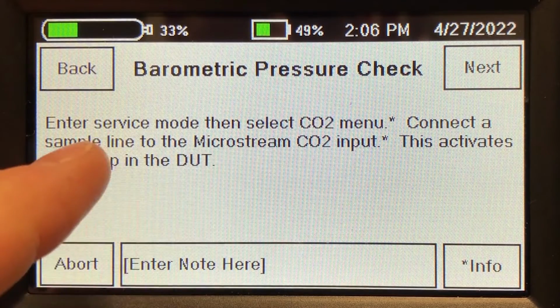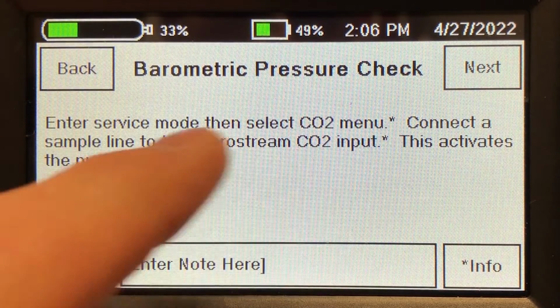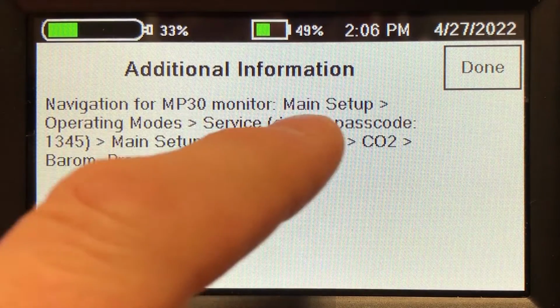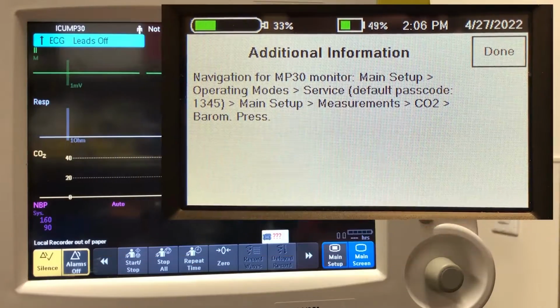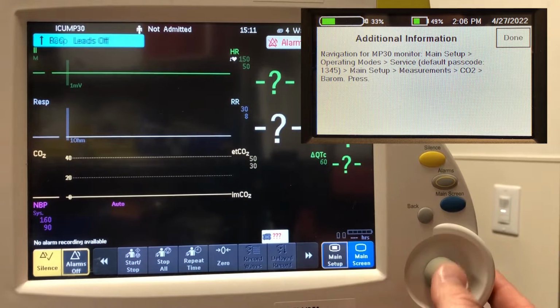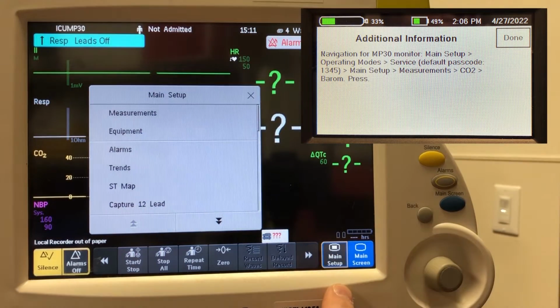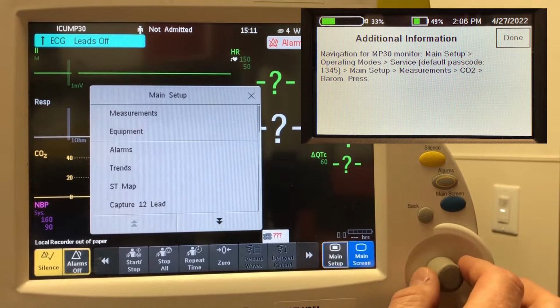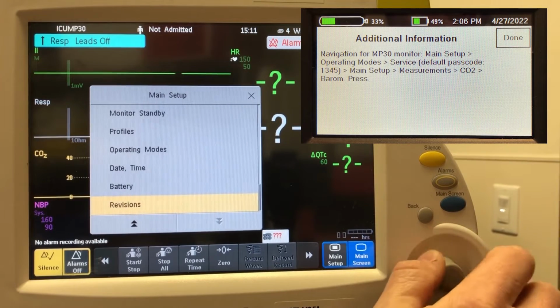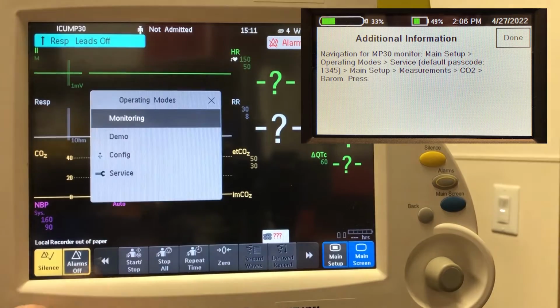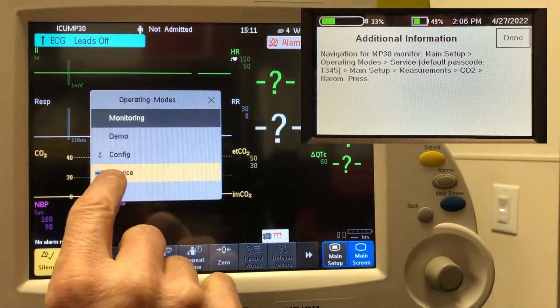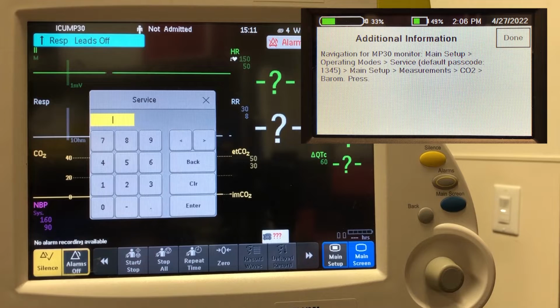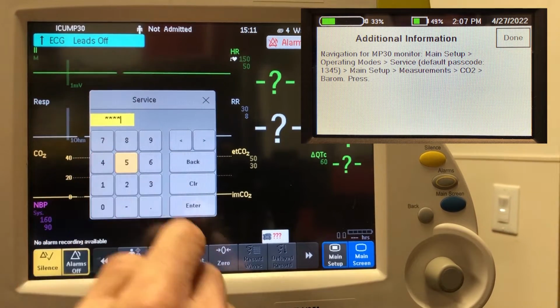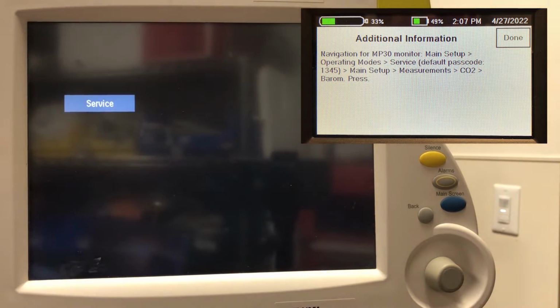So we go into service mode. If you don't know exactly how to do that, touch info, and this gives you the navigation for an MP30 monitor. So we start by touching main setup, and then scroll all the way to the bottom for operating modes, and we select service, and we've got to enter, and you see over here on the smart tank we give the default 1345 passcode. Now we're in the service menu.